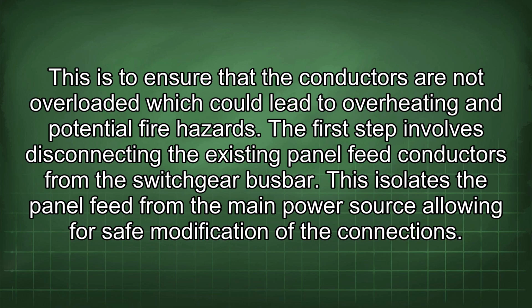The first step involves disconnecting the existing panel feed conductors from the switchgear busbar. This isolates the panel feed from the main power source, allowing for safe modification of the connections.